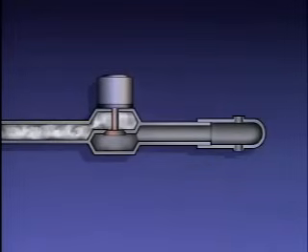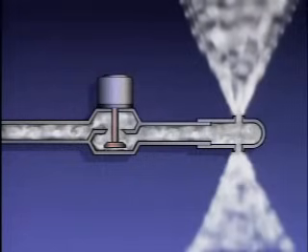When the valve is open, a blowing medium is sent through the feed tube under pressure and discharged through the nozzles in the lance tube. There are two general types of soot blowers found in most boilers: wall soot blowers and long retractable soot blowers. The main difference is the distance they can be inserted into the boiler. Wall soot blowers can be inserted a short distance into the boiler furnace to remove soot from the water walls, while long retractable soot blowers can often be inserted more than half the width of the boiler and are used to remove soot from superheaters and reheaters.